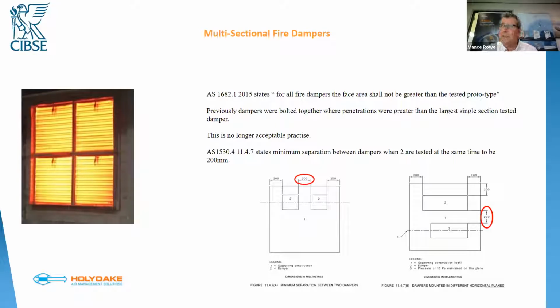In fact, that's no longer an acceptable practice. We've found in subsequent testing that when you bolt a series of dampers together on the sleeves, the sleeve areas open up, and that allows transfer of fire and products of combustion through those apertures. So multi-section dampers, like all new fire dampers, now need to be tested in their own right. And it's absolutely critical that people understand this. I will cover the grandfather clause in a little bit more detail as we go further forward, which currently means that it's acceptable practice to screw fire dampers together, providing you've got a test report that covers that type of installation. I've also got there that AS 1530.4 clause 11.4.7 states the minimum separation between dampers is 200 millimeters when tested.